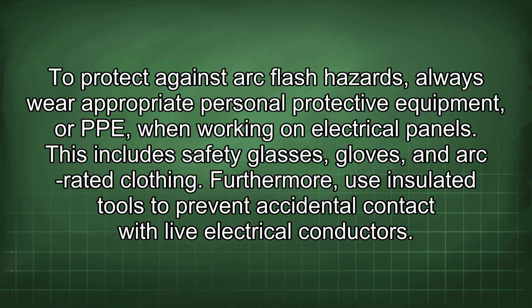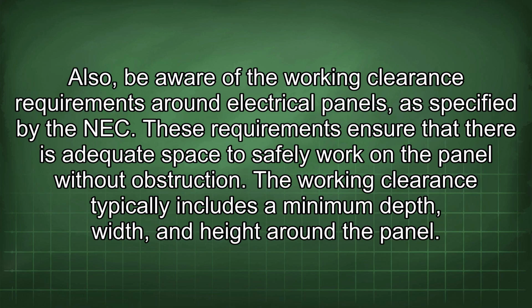To protect against arc flash hazards, always wear appropriate personal protective equipment, or PPE, when working on electrical panels. This includes safety glasses, gloves, and arc-rated clothing. Furthermore, use insulated tools to prevent accidental contact with live electrical conductors. Also, be aware of the working clearance requirements around electrical panels as specified by the NEC. These requirements ensure that there is adequate space to safely work on the panel without obstruction. The working clearance typically includes a minimum depth, width, and height around the panel.